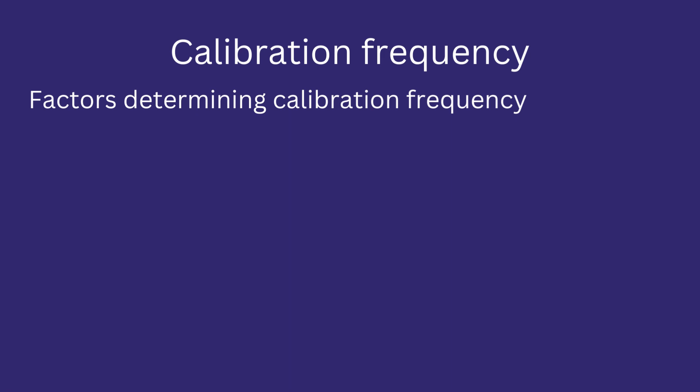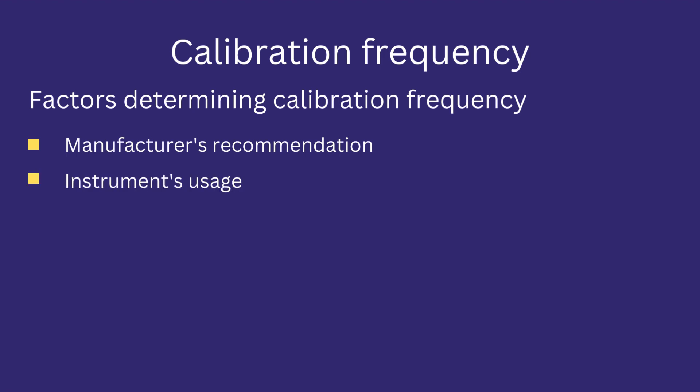Some factors that determine the calibration frequency include: Manufacturer's recommendation — setting the frequency of calibration according to the guidelines of the instrument manufacturer. The manufacturer provides various options for selecting the calibration frequency, which can be found in the maintenance or troubleshooting manual of an instrument. Instrument usage — selecting the calibration frequency according to its usage. If an instrument is frequently used in a pharma process, it can be calibrated more frequently. On the other hand, if an instrument is less frequently used, its calibration frequency can be less.